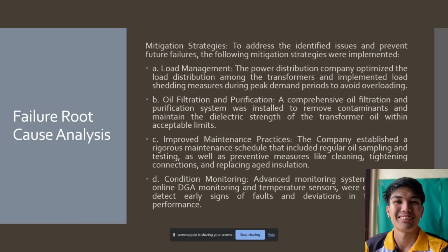B. Oil filtration and purification. A comprehensive oil filtration and purification system was installed to remove contaminants and maintain the dielectric strength of the transformer oil all within the acceptable limit. C. Improved maintenance practice. The company established a rigorous maintenance schedule that included regular oil sampling and testing, as well as preventive measures like cleaning, tightening connections, and replacing aged insulation. And D. Condition monitoring. Advanced monitoring systems such as online DGA monitoring and temperature sensors were deployed to detect early signs of fault and deviation in transformer performance.